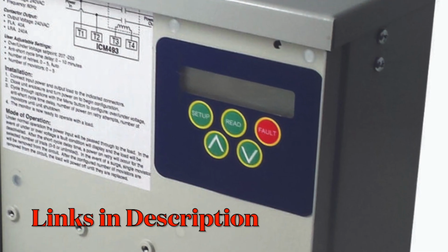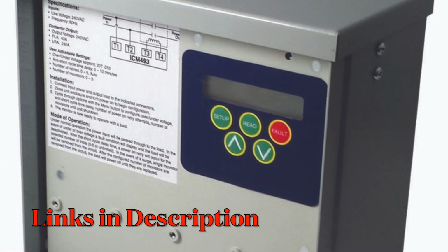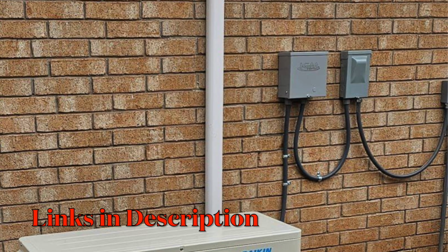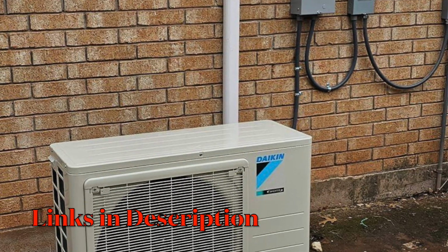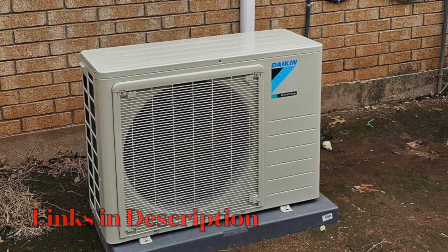The other good thing about phase monitors, if installed correctly, unlike a surge protector that's just wired parallel with the wiring, is they don't break the power in any way — they just absorb those surges. Instead, a phase monitor will actually break power; there's an in and an out, and if there's a problem, it won't allow it to go out. So it's just a much better form of protection.